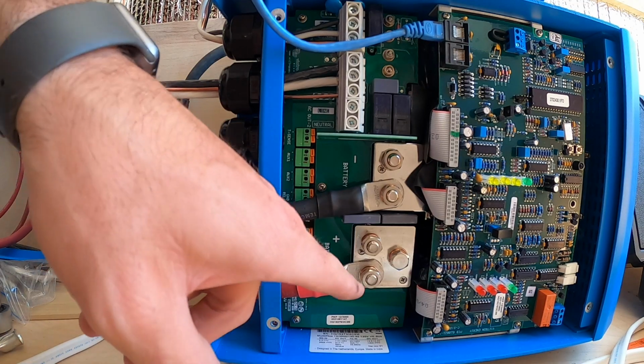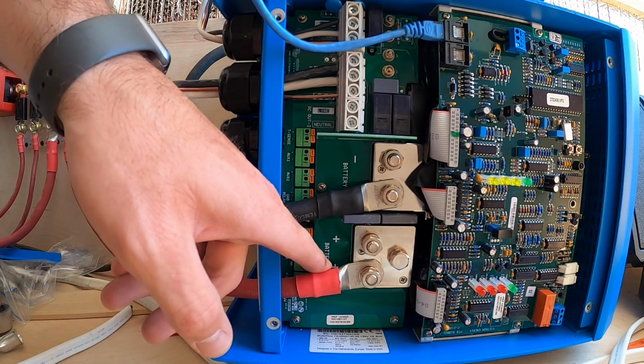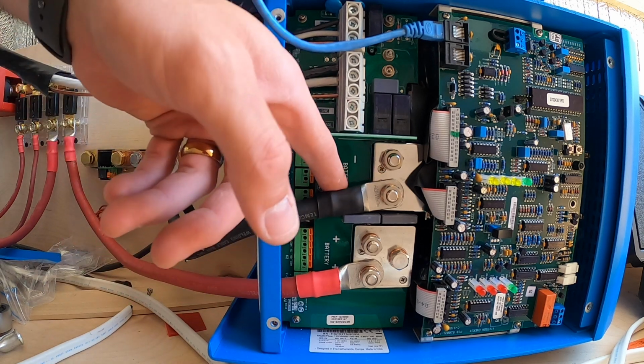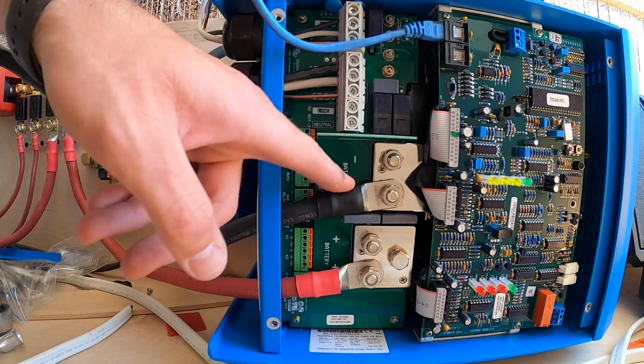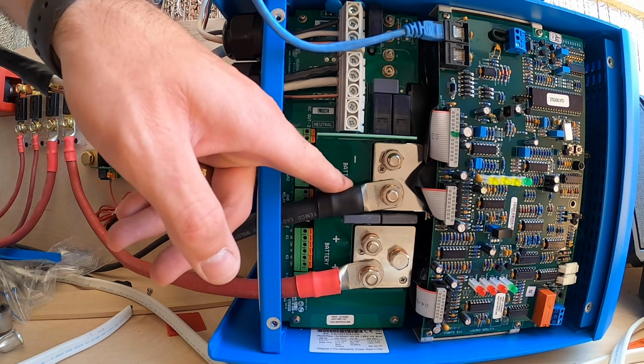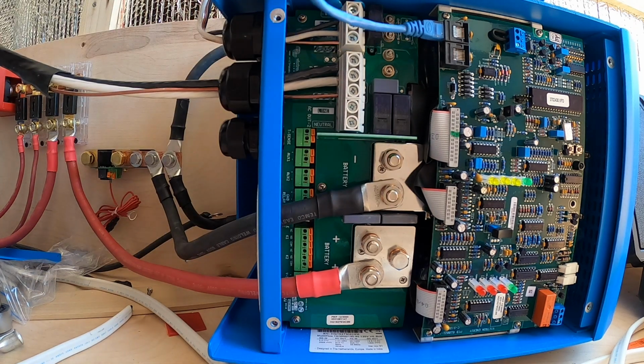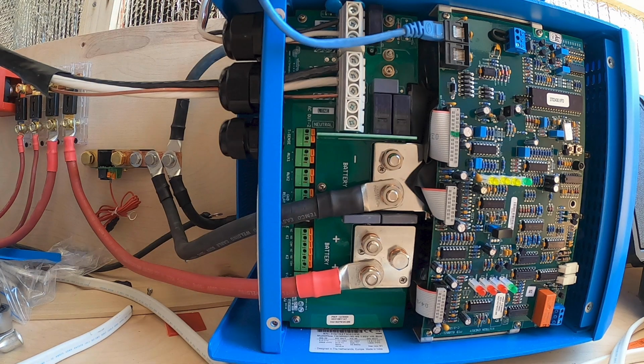Victron actually recommends using 2 2-aught cables for each terminal connection on both the positive and negative lead, which is why you see more than one bolt on each terminal connection. However, I only ran 1 cable for each, and I'm going to monitor this over time. From my initial tests, everything worked pretty good, I could even power a hairdryer, but this is a good example of where you may want to consult a professional and ask a certified electrician.